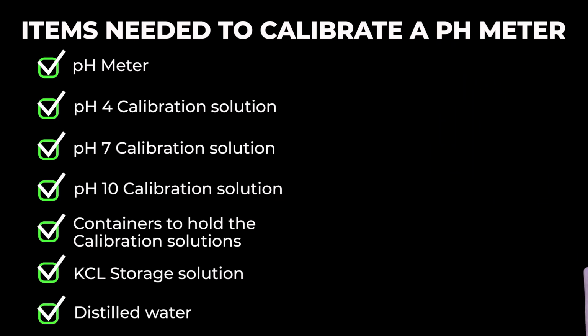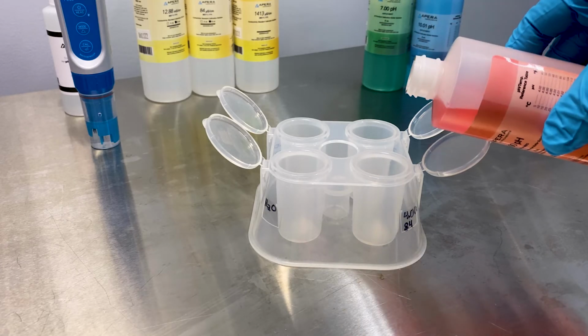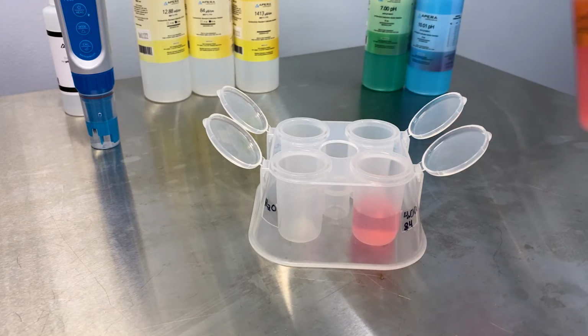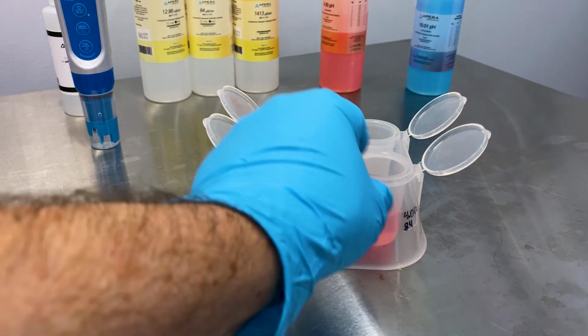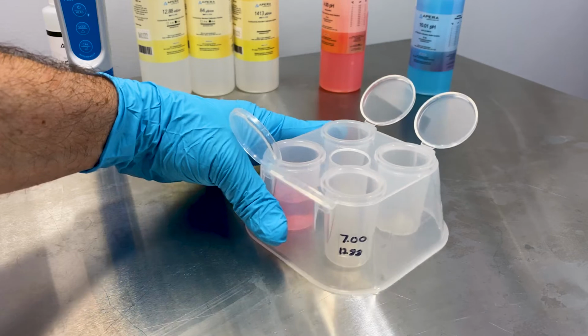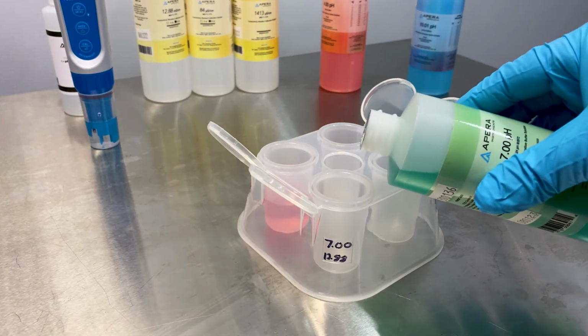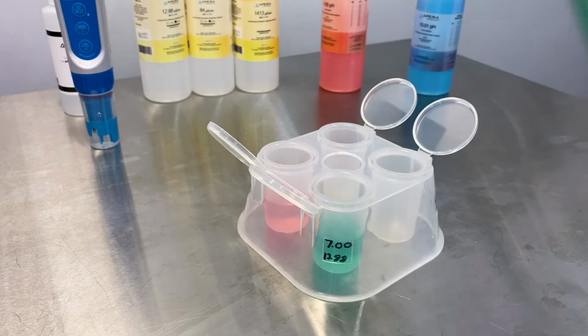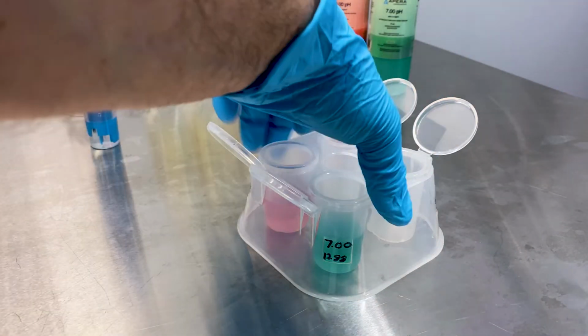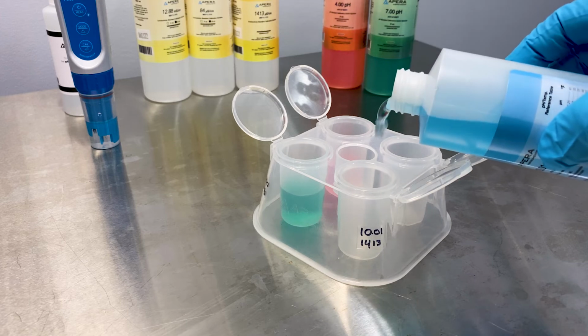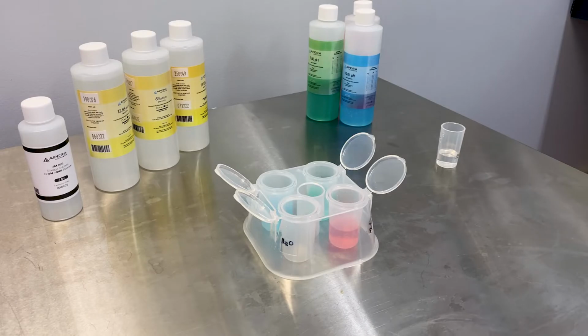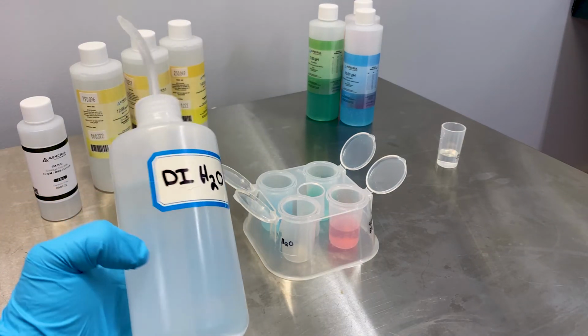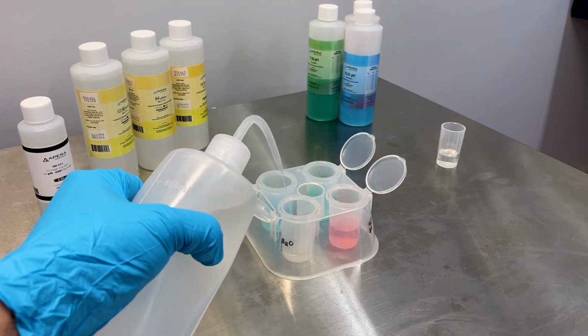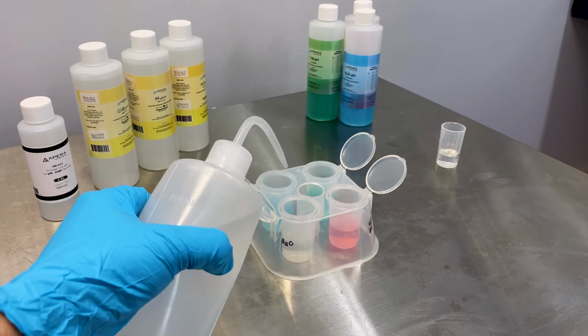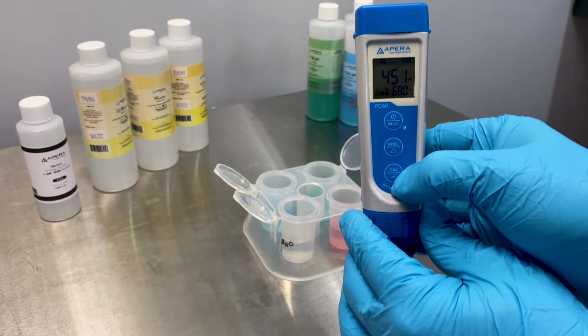Now for the calibrating. Start with pouring the calibration solutions into your containers. One container for each solution, and label them. This is another reason I like this container. Labeling and staying organized is really easy. I also put my EC calibration numbers on there so I can quickly calibrate my EC meter as well. I like to use the last compartment for distilled water. I use it for rinsing the meter between solutions and as a holding container if needed. I always keep a bottle like this in my pH kit for rinsing the meter in the field or when calibrating it. Cool, we are ready to calibrate.